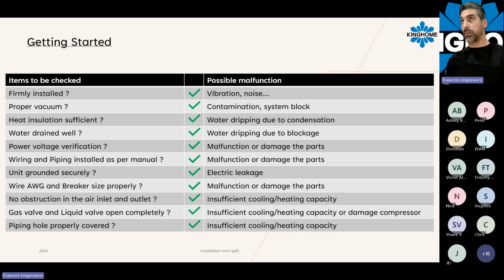Back in the day when we used to do service calls, that's what happened very often, not every time, but very often. Sometimes the installer just forgot to insulate the hole properly and cover it properly. So in winter time, for example, we had a call saying that the system is overshooting in the room. The homeowner was asking for 21, and it was always 24, 25 in that room. Looking at the system, it was performing well. We didn't find out why the system was overshooting, and then we figured out it was because there was not enough insulation in the wall anymore.